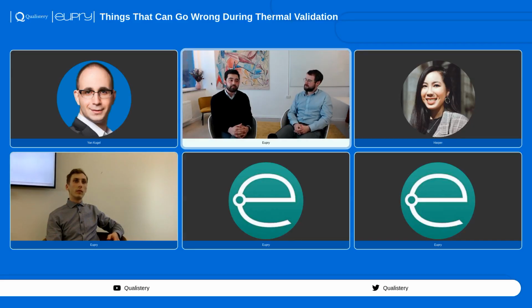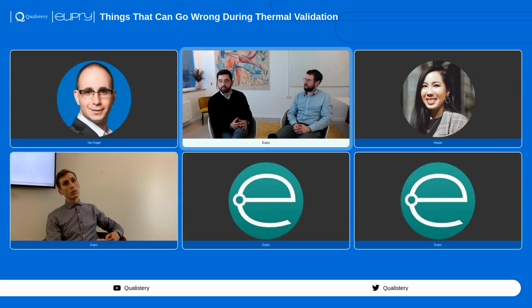It also depends on what kind of equipment you use, and what type. You require technical knowledge about the supplier you choose. If you have sensors you do have technical knowledge about, you can understand the drifting of that sensor will be very low. Then you can do a risk assessment about not doing an end calibration and just having an entry calibration. On the other hand, if you have old units you don't trust, thermal sensors that are drifting much, and you have that knowledge, then you're prone to do the end calibration to make sure the data is valid.